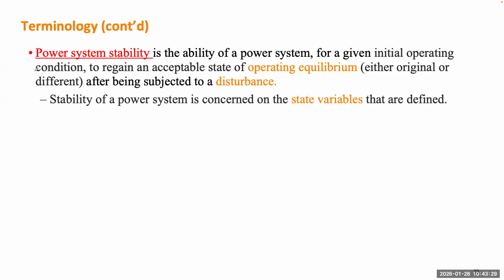The stability of a power system is concerned with the state variables that are defined. Because the entire power system has so many variables, some are variables of its generators, some of transformers, some of controllers, and there could even be very detailed control logic in the power plant. As power system operators, if you want to make sure the entire system is stable, some very detailed variables are not very important. So they want to focus on only the operating quantities, such as the voltage, current, power, or frequency, as the most important variables. So they will define the state variables. They want to make sure those state variables are able to go back to the equilibrium after a disturbance.